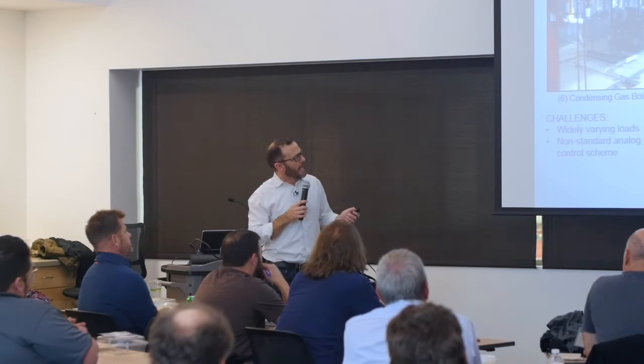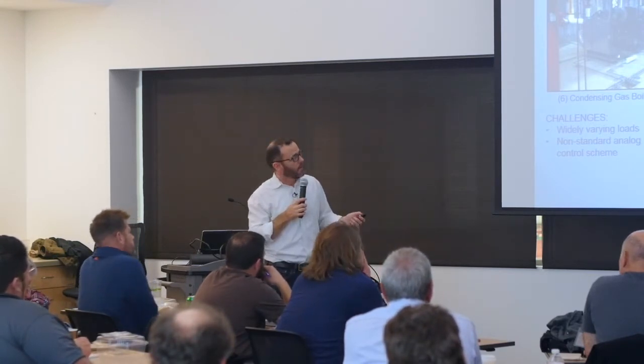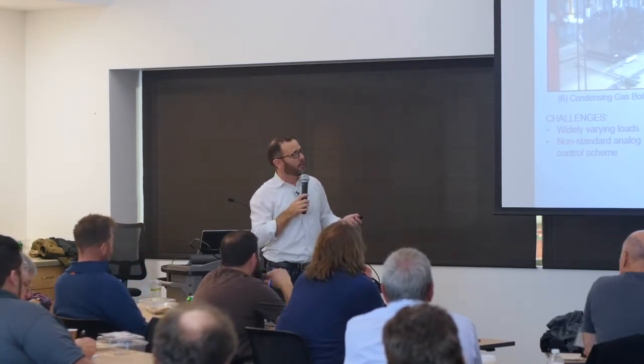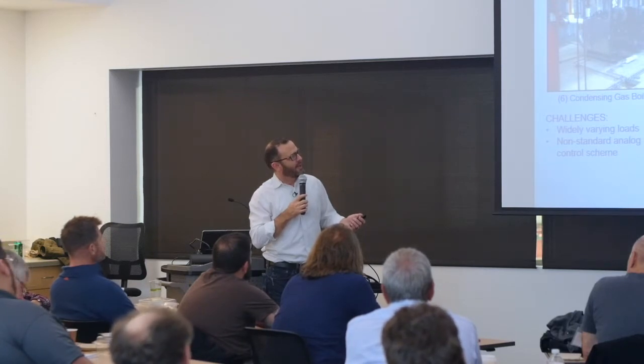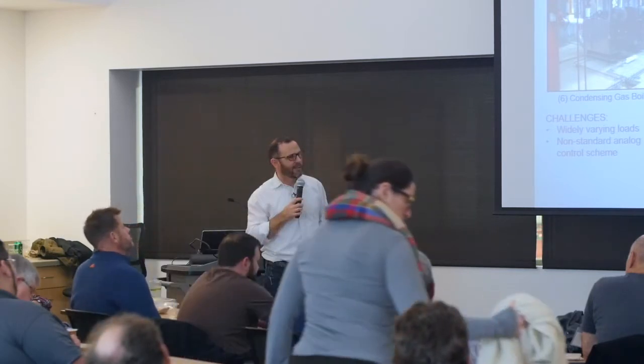I did some research on them. And they actually have an analog 4-20 milliamp control to control their loading, and then they also have an enable into them. But to actually turn them off, you have to bring the 4 to 20 milliamp down to zero. Well, this building's Apogee system, the Siemens system, can't output zero milliamps on their analog output. So I ended up putting in a bunch of little relays in here to completely disconnect the analog signal so that they could actually unload when they were in the off-duty, basically.